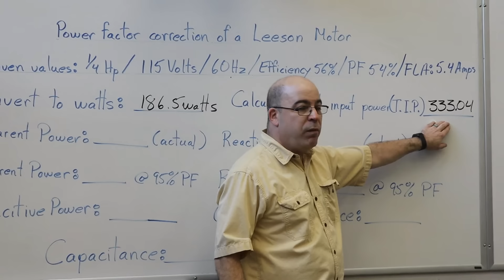Total input power, 333.04. Next, we're going to calculate apparent power. We're moving on to step 3, calculating the apparent power of the motor. Now, to do this, what we're going to do is take the listed value of power factor, and I'm going to divide the total input power by it, and that's going to give me the apparent power of the machine. Now, apparent power means that we're taking into consideration all of the reactive power and the true power the motor requires. And this is a really important step in understanding how to calculate for power factor correction. So let's start plugging in our numbers.